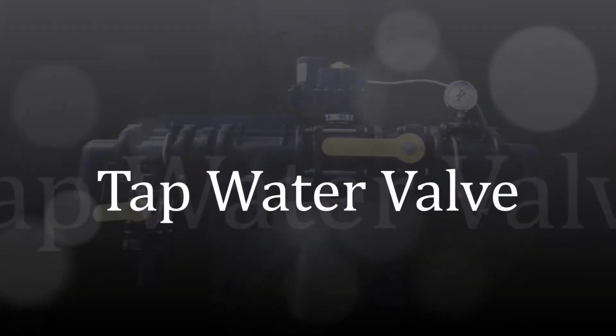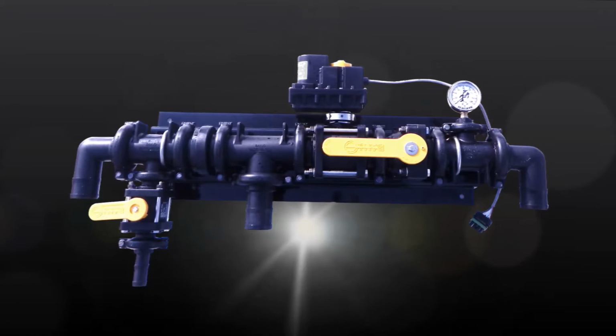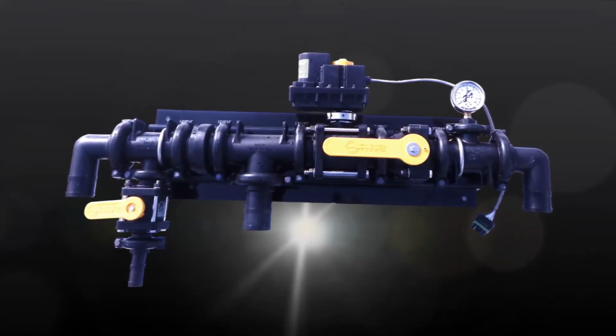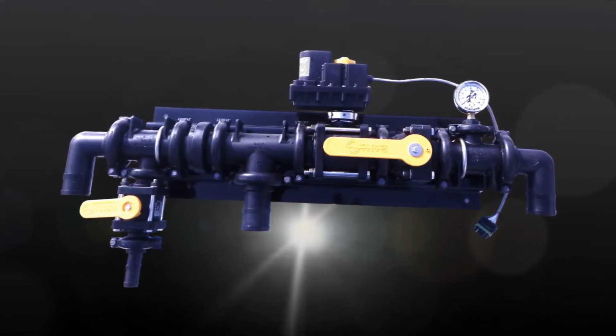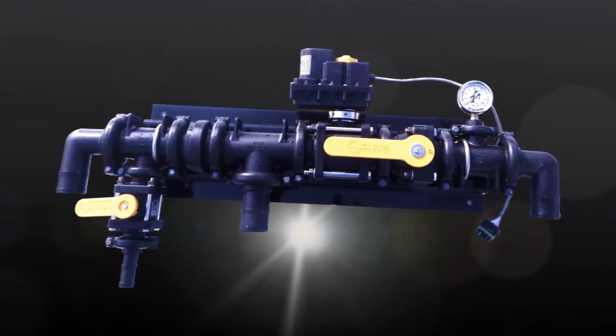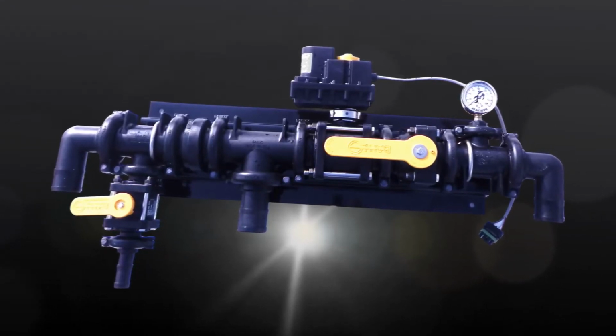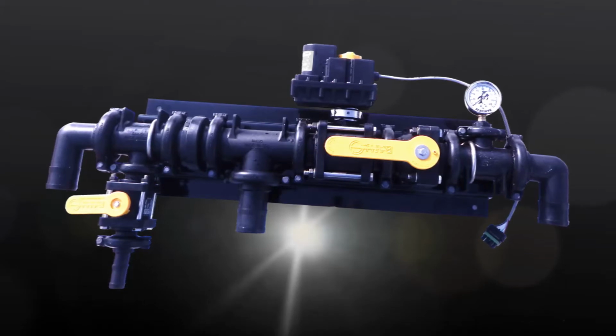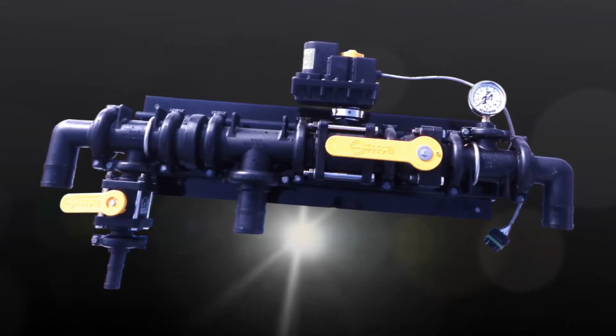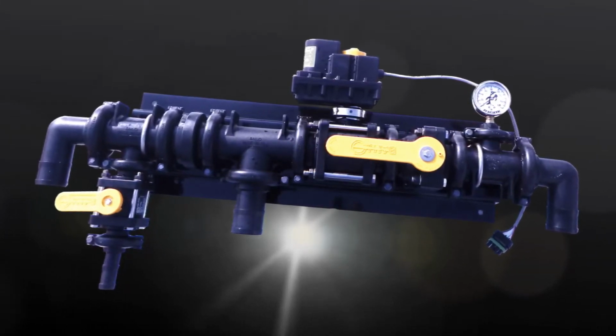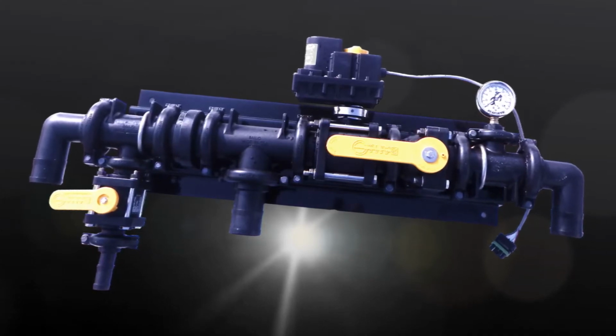When more water is needed, it is added to the concentrated recirculating brine through the electric tap water blending valve. Blending incoming water with brine before it enters the hopper ensures that the brine hoses are filled with partially saturated brine to prevent freezing, and that proper salinity is reached more quickly and maintained while adding fresh water.